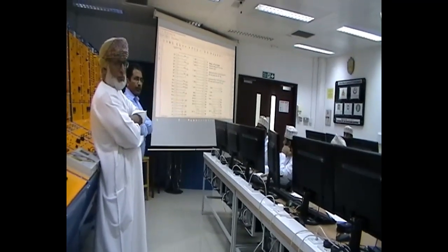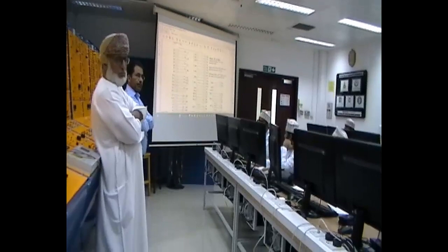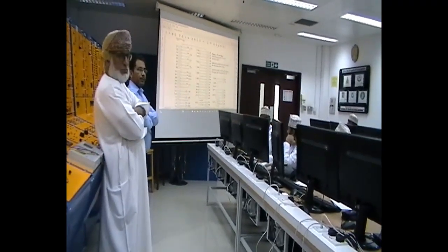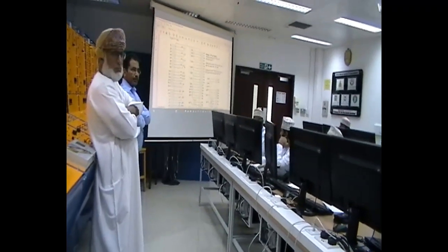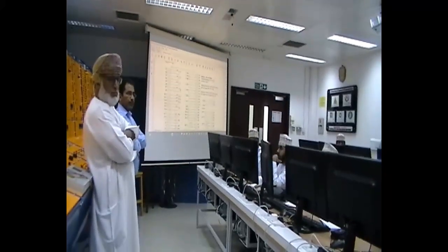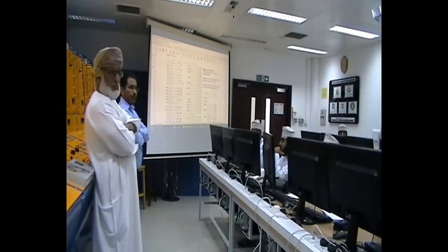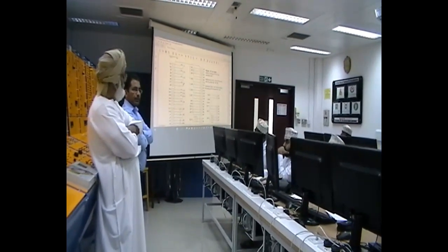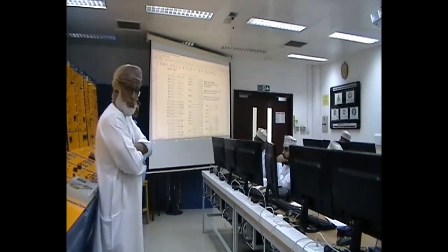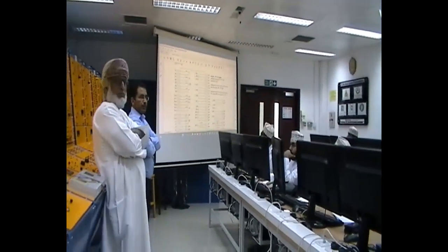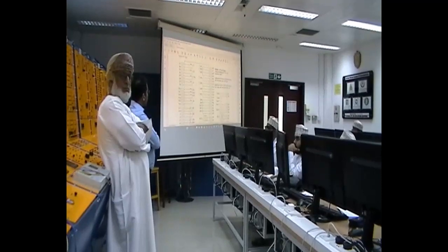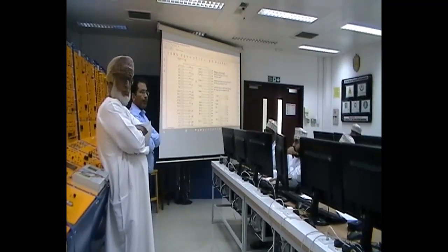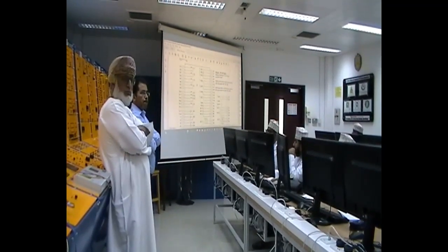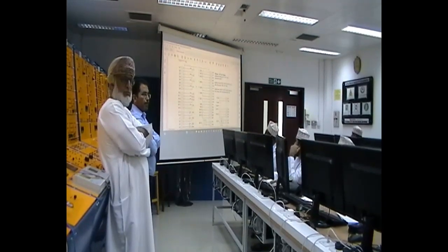For residual current, but sometimes it comes from a separate CT. If it is CBCT and it's protecting an overhead line, we'll use a CBCT. We'll connect I4 to the separate CT, and the rest of the CTs will be in star connection. But we don't always have the CBCT, so we'll connect along with it the neutral from the three CTs.